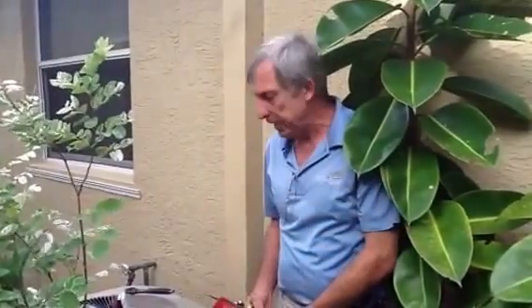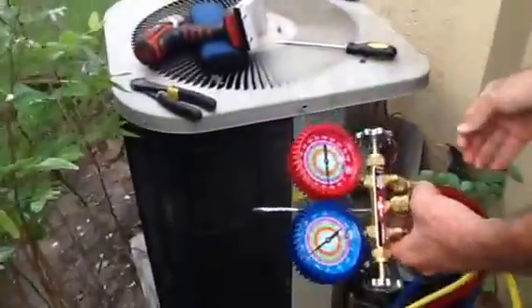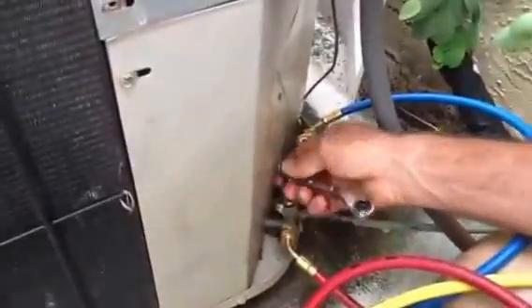The basic tools that you need to do a pump down are just your service wrench right here. This is a two port service wrench where it goes not only on the high side of the liquid line but it also goes down to the suction line.